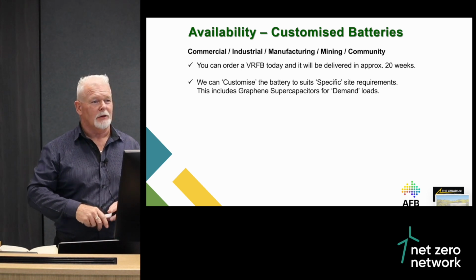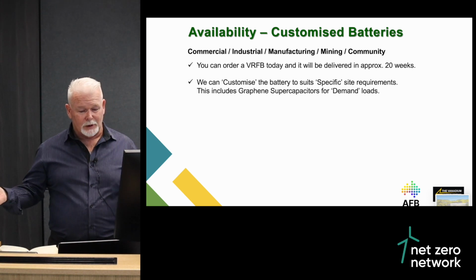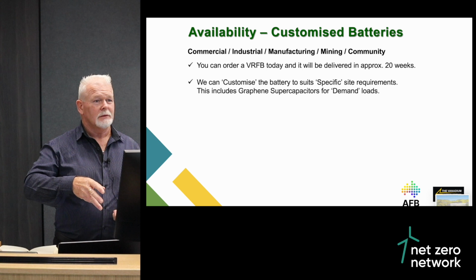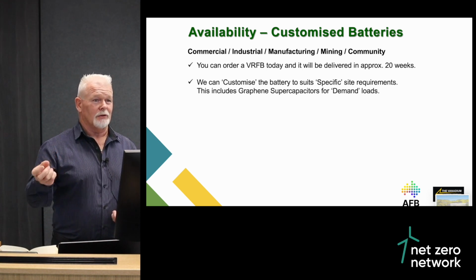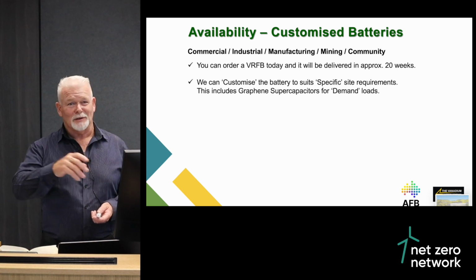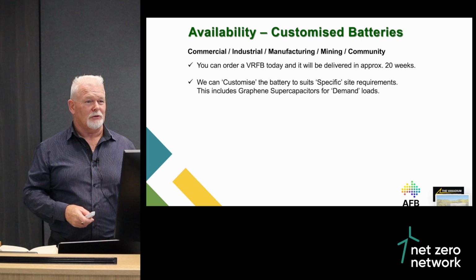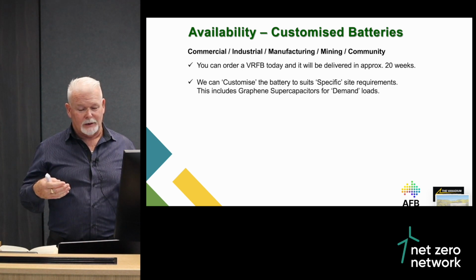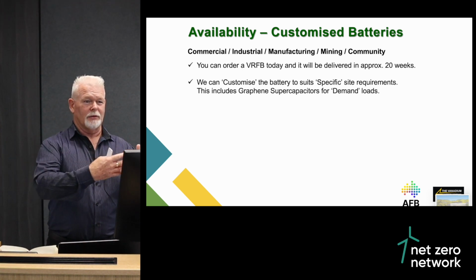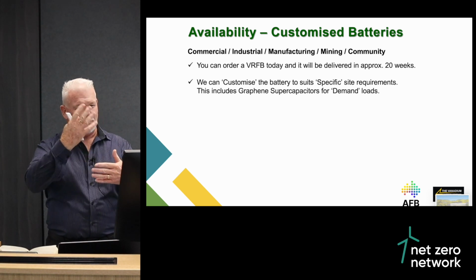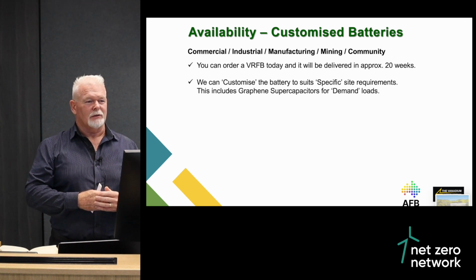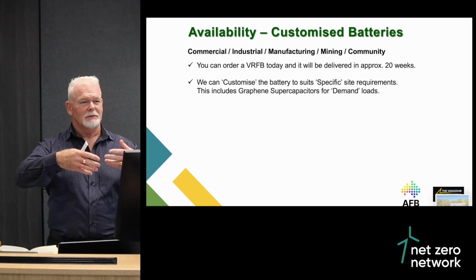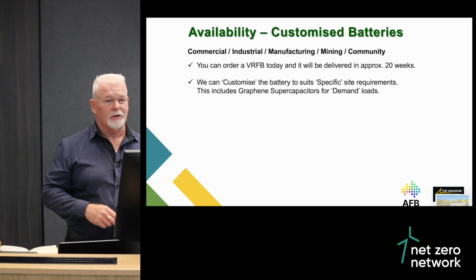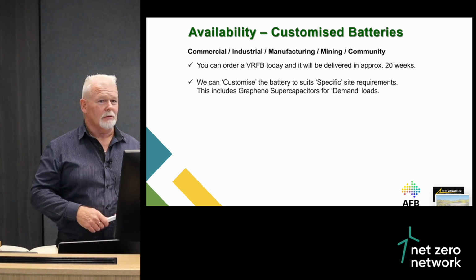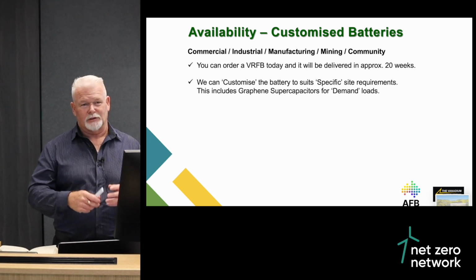If you've got demand the battery can't handle, we have a solution: supercapacitors that can take the spike and then discharge back onto the vanadium battery, which recharges the supercapacitor, and the cycle repeats. Putting a supercapacitor with a vanadium battery helps with demand, like two sisters together. Two years ago people were talking about pairing a lithium battery with vanadium to handle spikes, since lithium has better demand capacity, but I said that's putting a non-flammable battery with a flammable one - not really the outcome we're after. Supercapacitors are a better match: non-flammable, 20,000 cycles, a great sister to the vanadium battery.